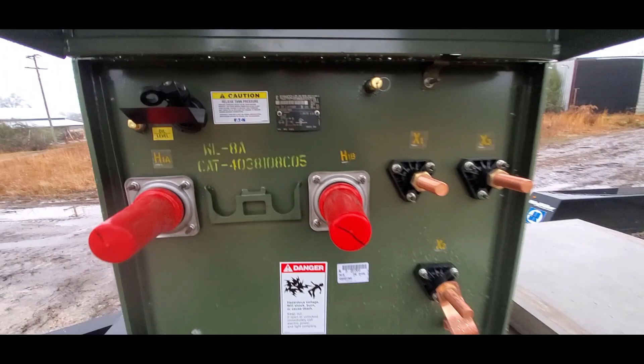Well, I'm not an electrical engineer, I'm a mechanical engineer, but I looked up this part number, and this is a distribution transformer made by ERMCO, made February of this year, if you can believe that, and it's 100 kVA, and they only go up to 167 kVA for single phase. But I was trying to figure out what this meant, and this means that this is a 34,500 volt grounded Y. That's the incoming service. So it's 34,500 volts phase to phase, 19,920 volts phase to ground.